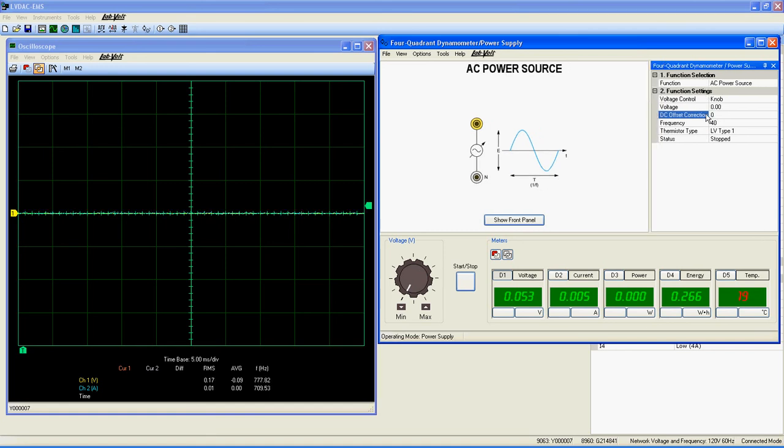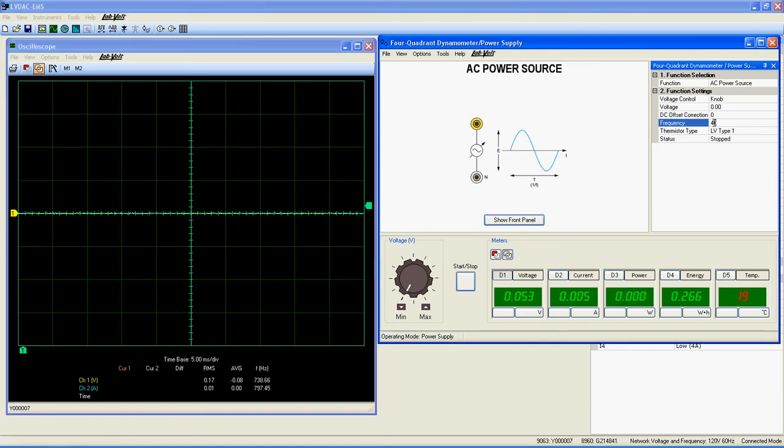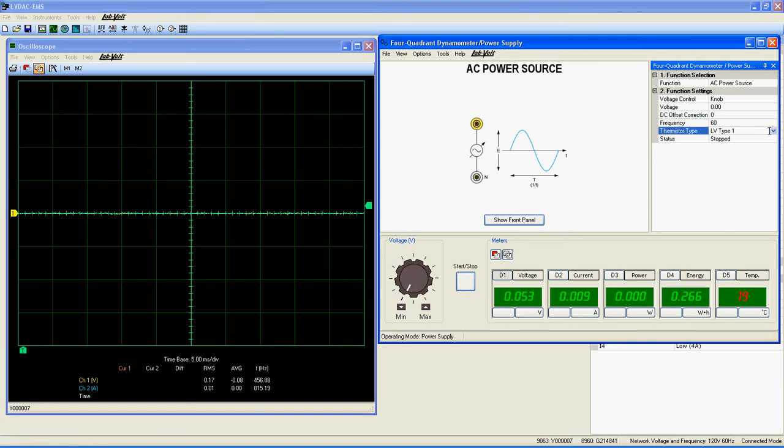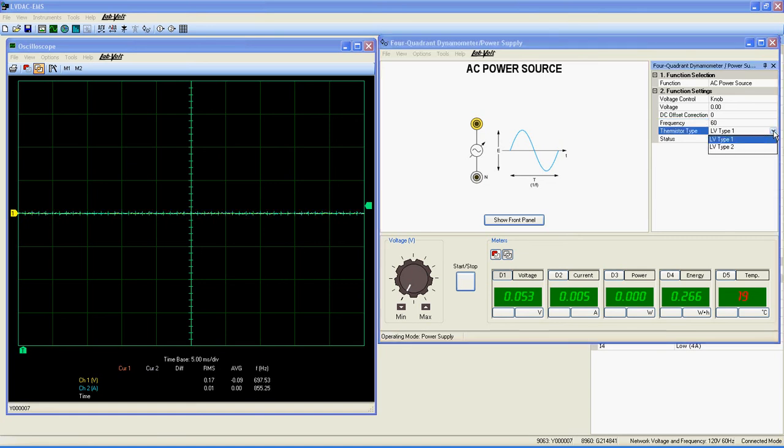DC offset correction applies a DC voltage to correct any DC offset that can be created by the load applied. Frequency: This setting controls the frequency of the output voltage. It is ranged from 10 hertz to 100 hertz.